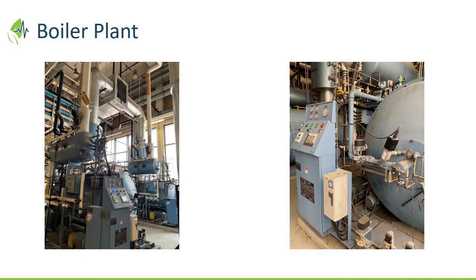Yeah, so there's an actuator right smack dab in the middle of the economizer in the photo on the left there. We found that's not even powered, and the position of the damper blade in the middle is unknown. This happens all the time in any facility anywhere in North America. That actuator is connected to a damper which opens up when you want to bypass the economizer, so then it's not recovering heat anymore. If the damper's open, the flue gas just goes straight up the stack as normal. If it's closed, it forces the flue gas around the heat exchanger, and you recover heat.